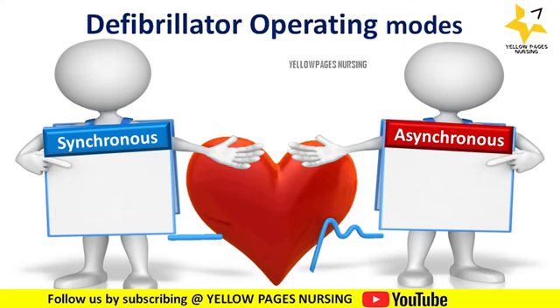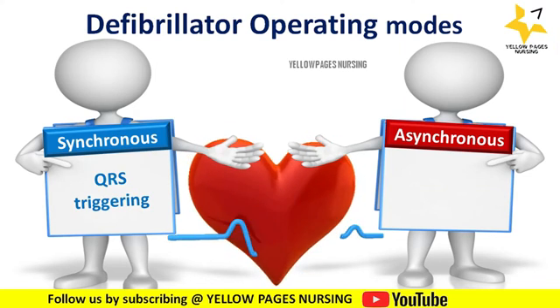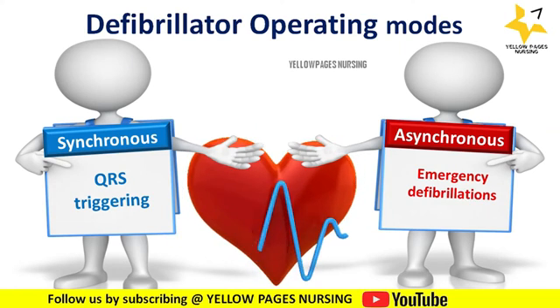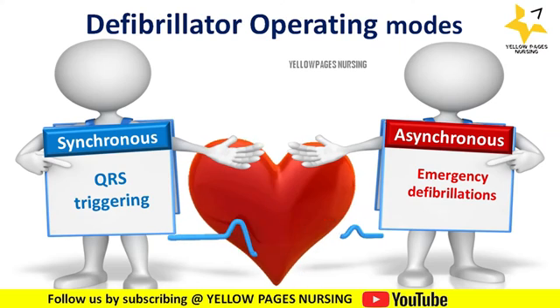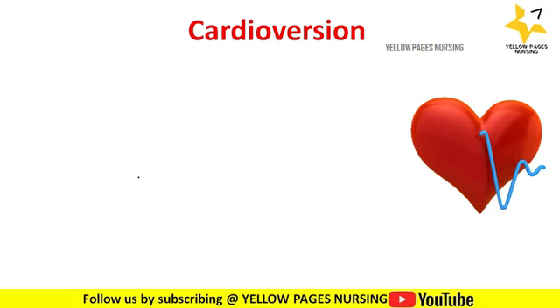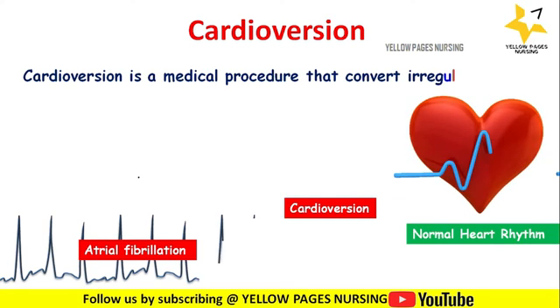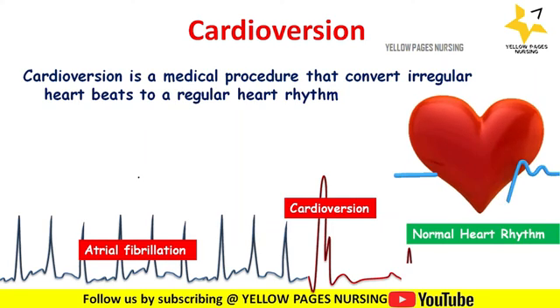There are two operating modes of a defibrillator: synchronous and asynchronous. In synchronous mode, the heart's own pulses are taken into account for QRS triggering. In asynchronous mode, it is reserved strictly for emergency defibrillation.